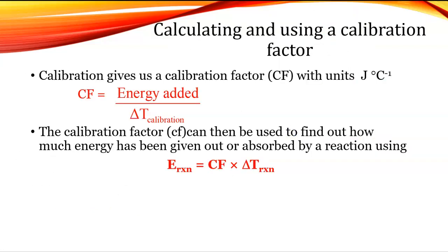Okay, so when we've done a calibration, you can create a calibration factor, shortened to CF. And its units are joules per degree Celsius, because we've got the joules that we added here, and we're dividing it by the change in temperature. So now you'll see maybe why I started using delta T of reaction, because we've got 2 delta T's sitting here on this slide.